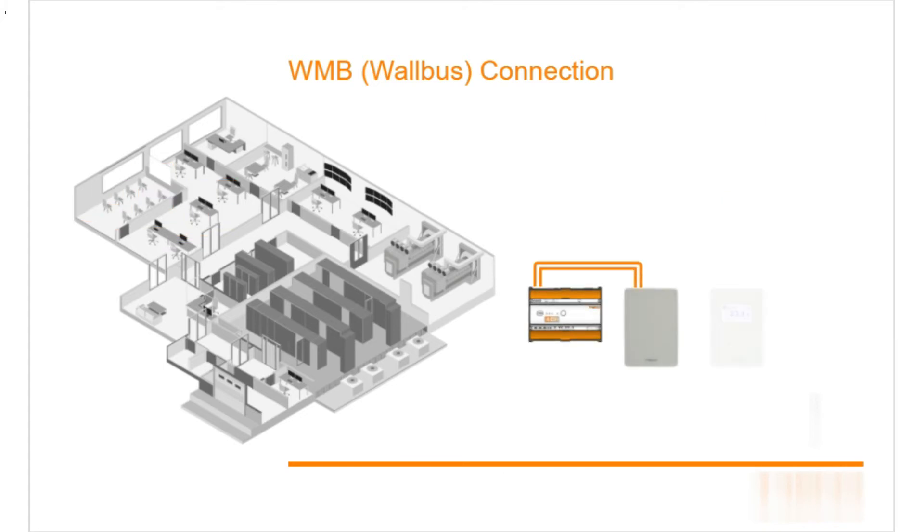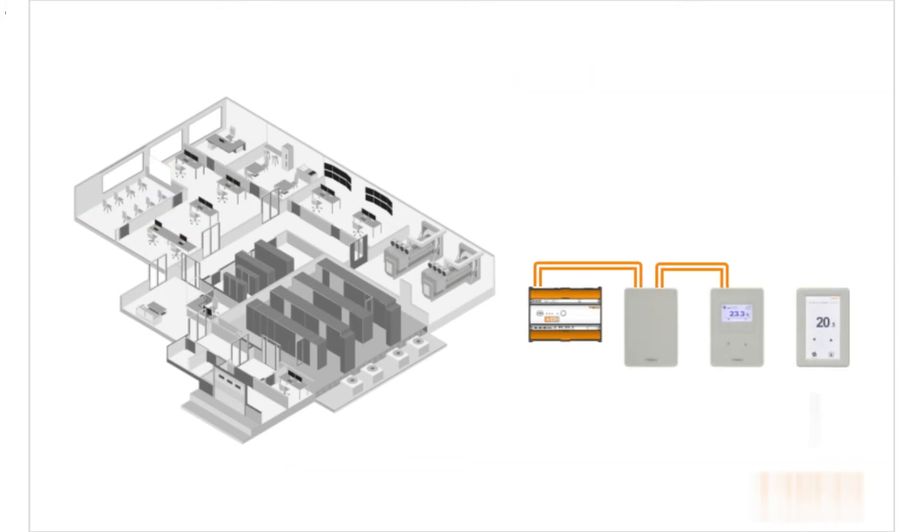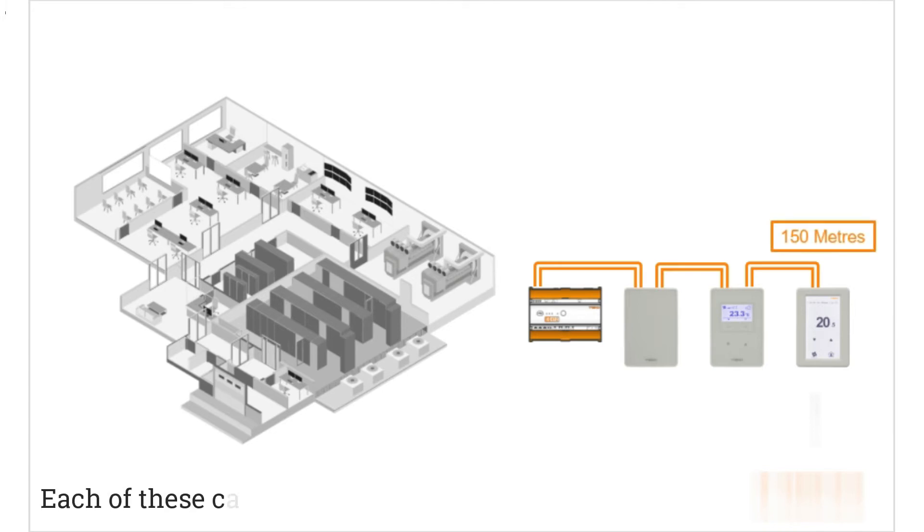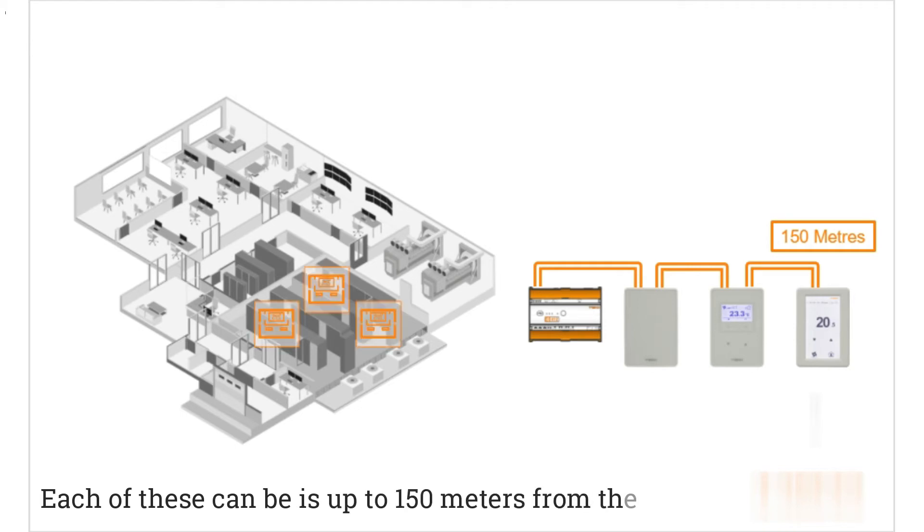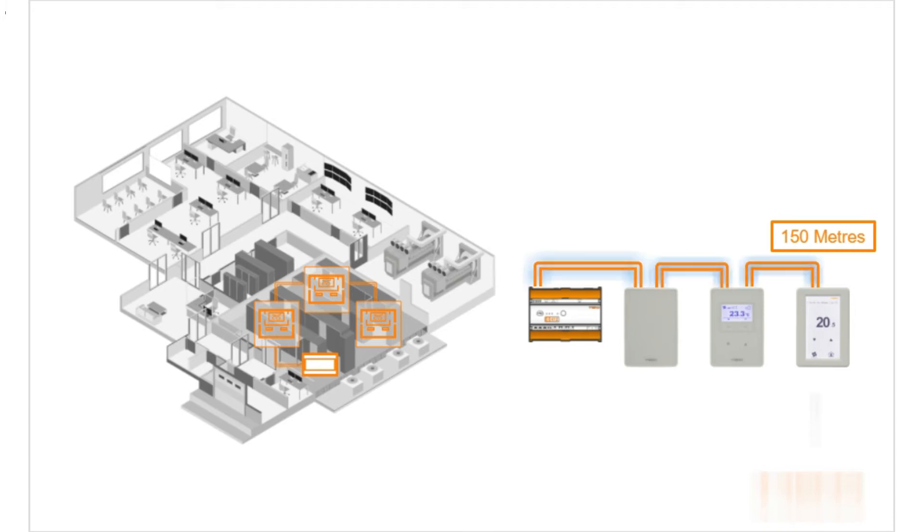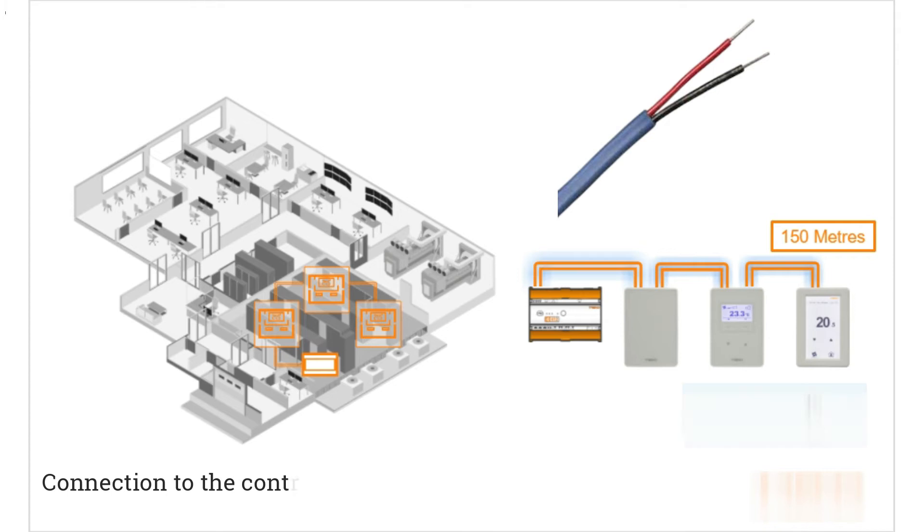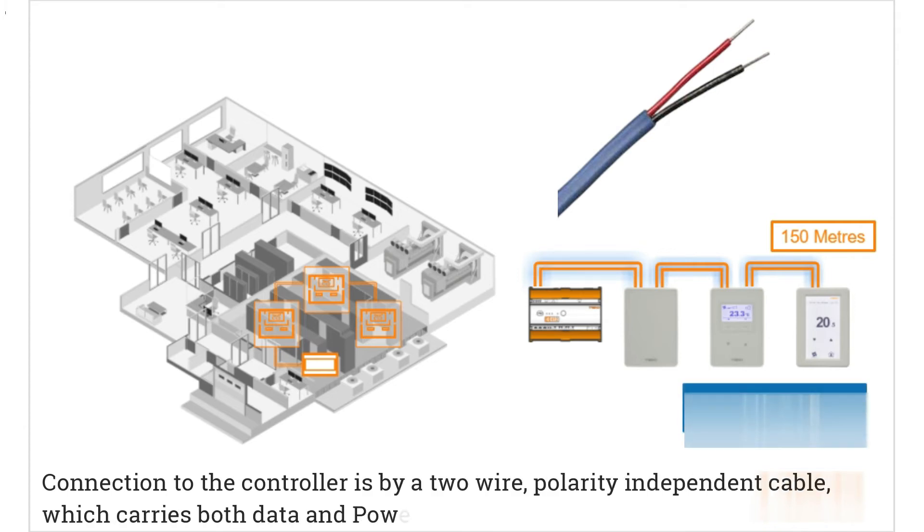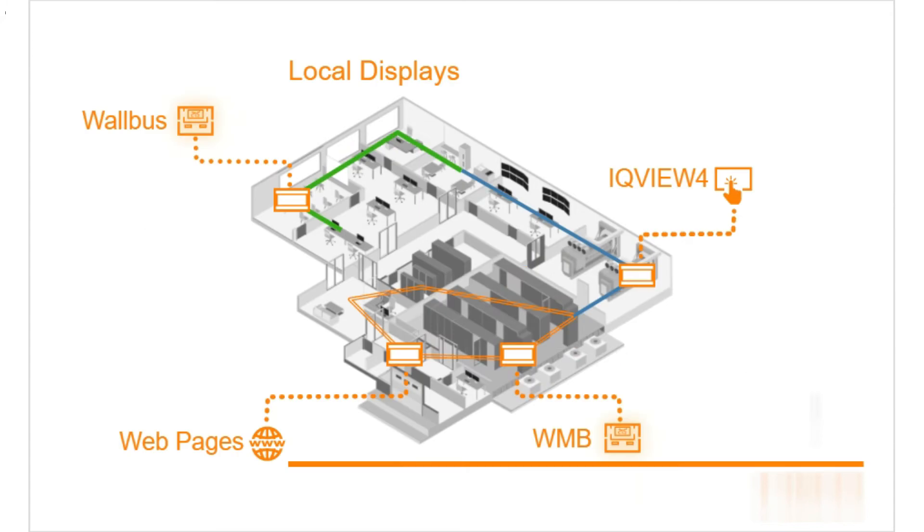As iQ4 controllers are generally more complex, they can have more WMB displays, up to 10. In fact, this depends on the type and power requirement. The farthest each of these can be is up to 150 meters from the controller, which is why in the server room we have several connected to a single iQ411 to have local visibility, but also extra sensors with instant feedback in the room. Connection to the controller is by a two-wire, polarity-independent cable, which carries both data and power.